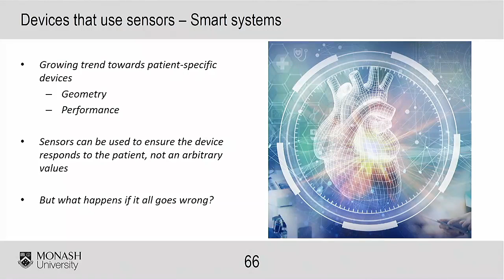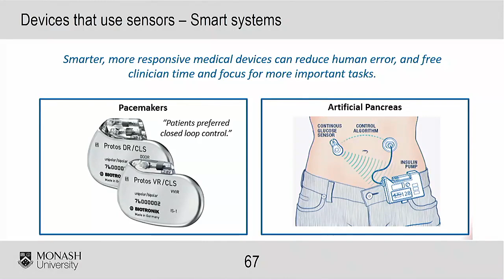But there are some control systems available in medical devices. Pacemakers use control systems to control the rate. We also see the artificial pancreas, which measures your glucose and then uses a control system to inject insulin. So they do exist, or they are under development with ventricular assist devices. For instance, active control is something that we're working on in our laboratory, and Andrew Stevens, one of the demonstrators, has done his PhD in this area. He's very good at it. Basically, we use pressure inside the heart to control the speed of the pump. So if the pressure goes up, we increase the speed, which reduces the pressure, and so on.